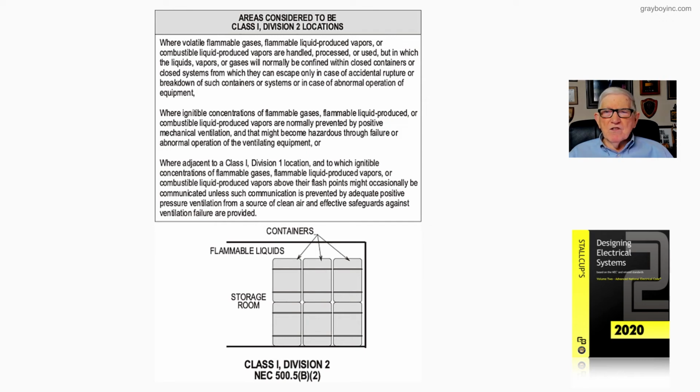And then remember that second evaluation, you're dealing with ventilation, where you could actually take a Class 1 Division 1 area and reclassify it as a Class 1 Division 2 area in accordance with the rules of NFPA 30 and NFPA 497 when you're doing the reclassification and providing the appropriate ventilation. So these are 3 evaluations in the NEC where we know we have a problem. Now we're going to solve that problem.